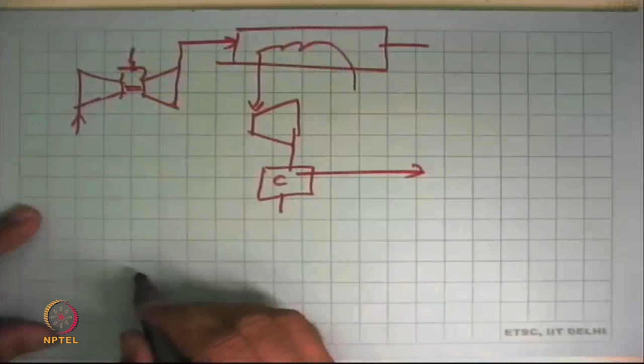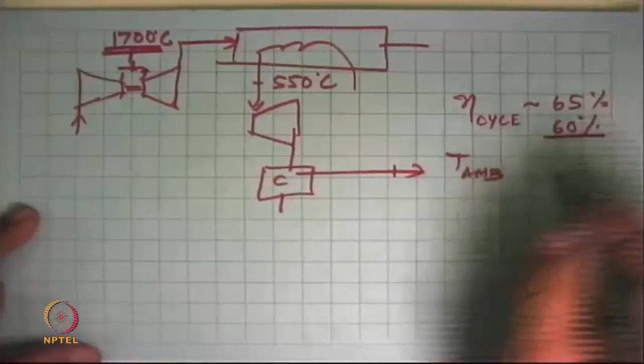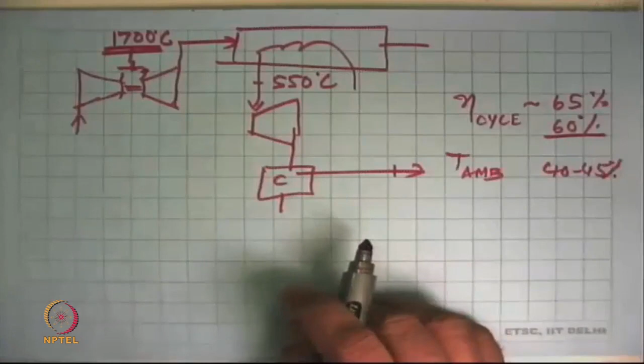So this peak temperature here is say 550 degrees Celsius. The peak temperature here was 1700 degrees Celsius. Your overall cycle, which is still a thermodynamic cycle, now operates between T ambient and this T_H. The result is that the cycle efficiency is much more than a coal-fired power plant, and some people are talking of 65%, 60% is already sort of achieved, and this is much more than the 40-45% that we get in a coal-burning power plant which produces steam and rejects the heat to the atmosphere. This type of plant is called a combined cycle power plant.